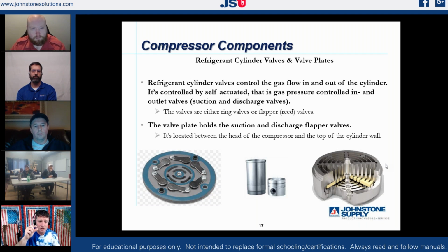Eventually, we're going to stress that steel, aren't we? Over time, we're going to stress that steel and it might not close properly, or we might get a piece of debris in there, and that snapping process will take that piece of debris and crunch it into the surface of our valve plate. And so then we lose some of the pressure that our pump is producing. That's how we can look at compression ratio and go, hey, my compression ratio is way off. I don't have much of a differential pressure here. I'm supposed to have a 2.5 to 1 compression ratio, and I'm running 1.6. And my refrigerant charge is proper, everything's running fine. What's my problem? My vapor pump.